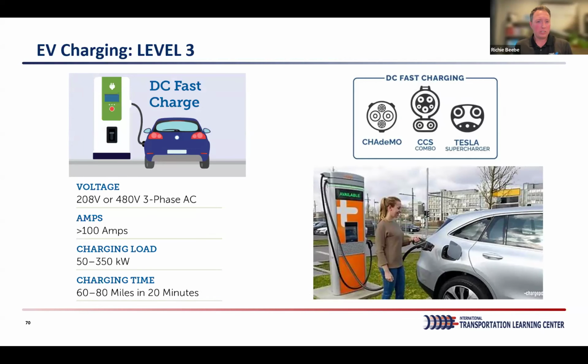So EV charging, the level 3 or DC fast charging - like I said earlier, this is typically 480 volts, 3-phase. It can be anywhere from 50 amps all the way up to 400 amps, and as this progresses, we could see even larger currents going to these chargers.